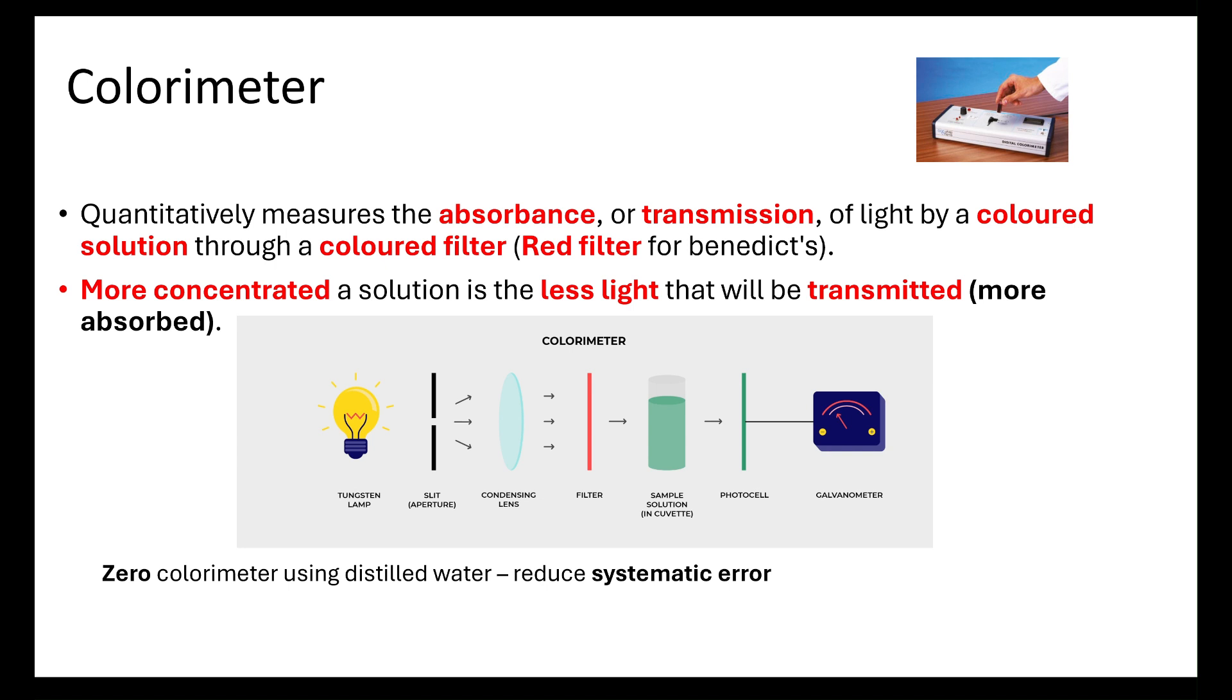There are a few things to note when doing a colorimeter test. We need to zero the colorimeter using distilled water to begin with. That is going to reduce our systematic error. The more decimal points we get with regards to our reading of transmission or absorbance, the increased resolution we have. We always want to repeat and calculate the mean. This is going to reduce our random error, our uncertainty in our data.